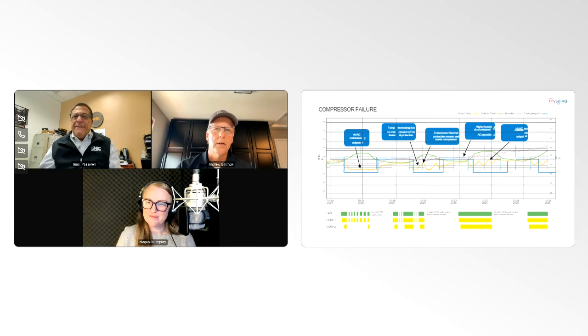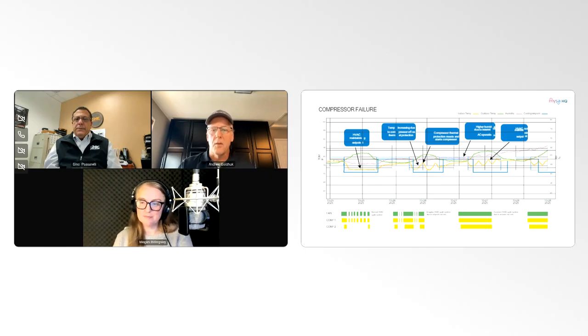And I think, for example, when a compressor or blower motor is failing, from a runtime perspective, you can see basically it's just simply not meeting heating or cooling set points. It could be working perfectly fine, and all of a sudden, you start to see a deviation away from set point. Could be an indicator of many different types of failures within the system itself. Something that is essentially disrupting the main part or the control circuits of an RTU that won't allow it to come on, whether it's high voltage or low voltage.